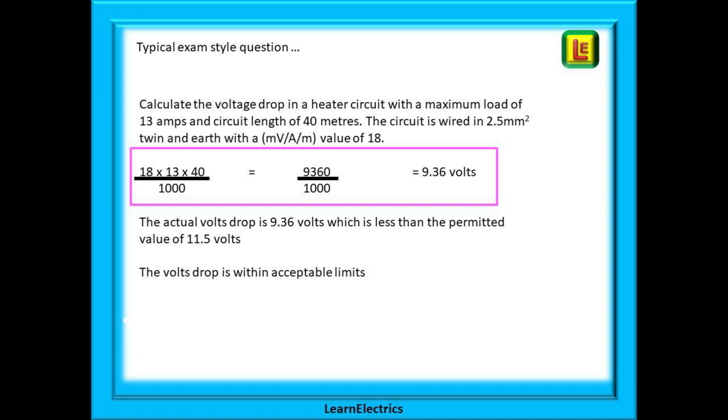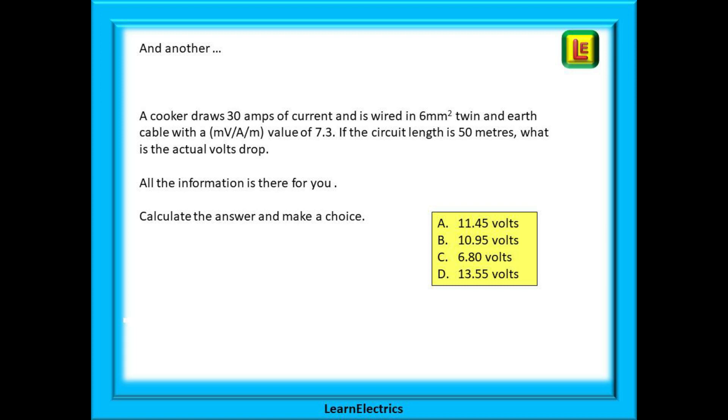This is less than the 11.5 volts permitted and is therefore an acceptable loss. And another, this time a cooker circuit. All the information you need is in the question. Pause the video whilst you work it out and then make your choice from the four that are offered. If you have done it correctly you should have an answer of about 10.95 volts give or take a tiny amount. And again this is within acceptable limits.